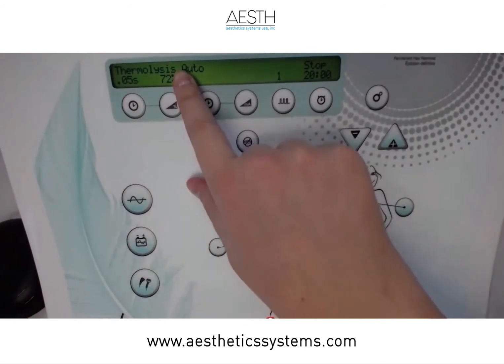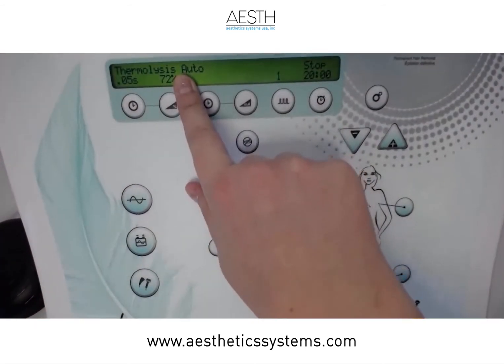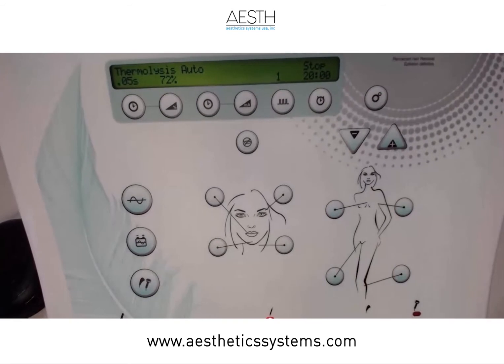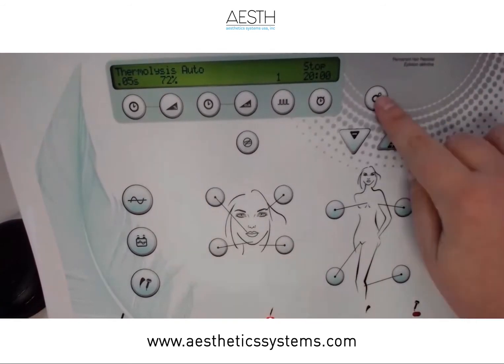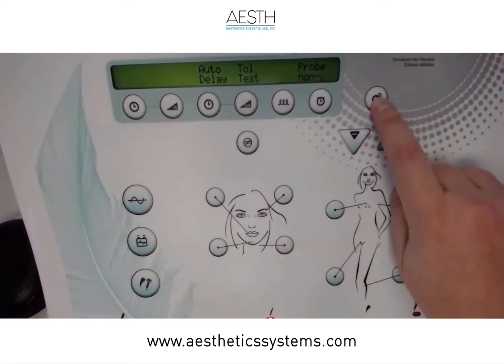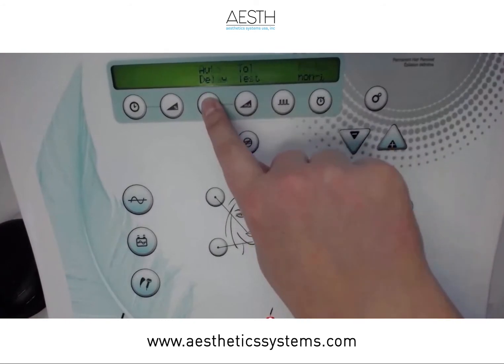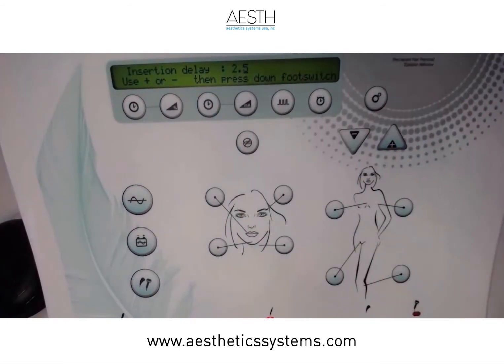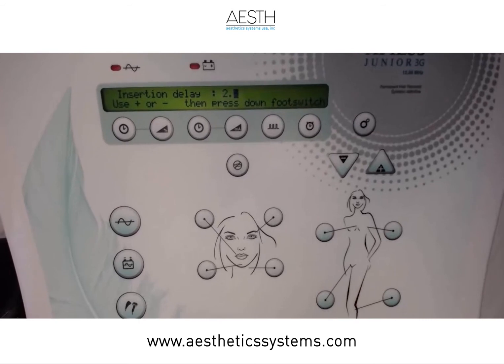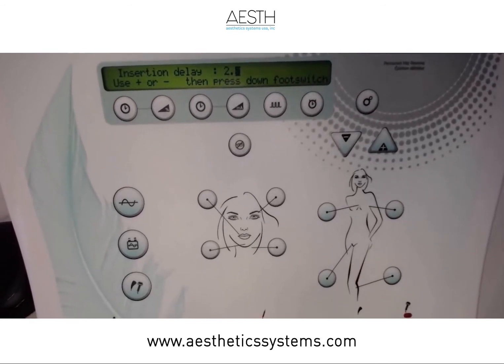So you give the client the ground, and you've got auto mode selected here. Now we may want to double check the auto delay. Remember our configuration key—our auto delay is here, so press right underneath it. This machine was set to a 2.5 second auto delay.